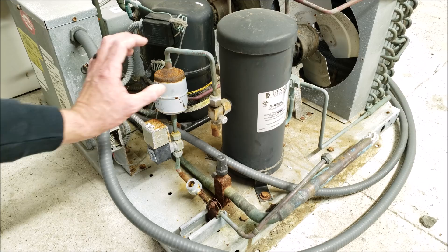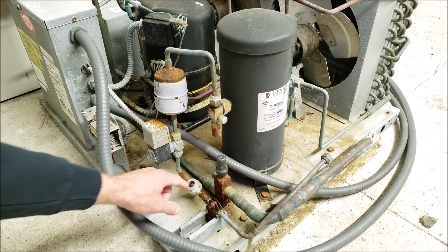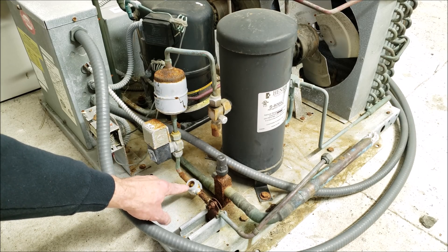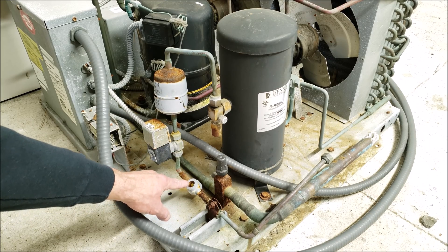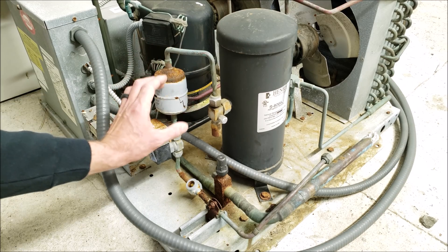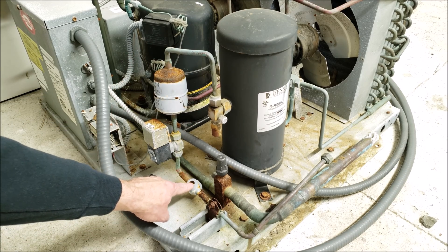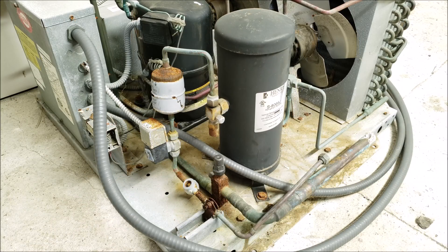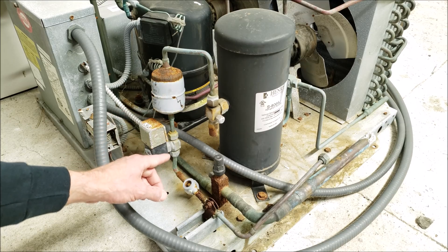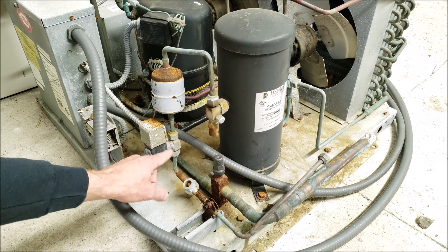You also want the filter dryer before the sight glass, because if the dryer were to get clogged, you could detect it at the sight glass by seeing bubbles. There would be a pressure reduction across the clogged dryer, so it wouldn't allow the full liquid flow through — and you'd be able to notice that at the sight glass. Since the filter dryer comes before the sight glass and the solenoid is in between the two, that establishes the correct order for all three components.